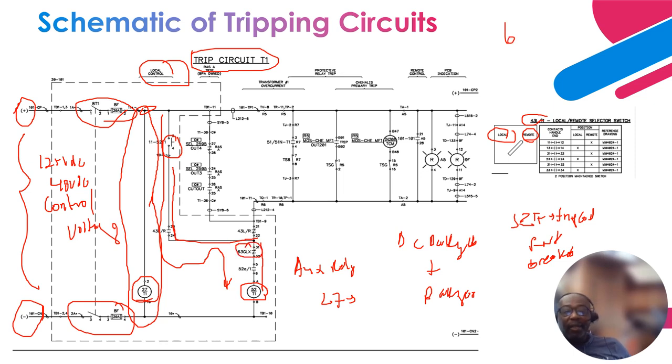So 63GLX is an auxiliary relay, a control relay, right? It is a gas switch relay. Basically, it's measuring the pressure and density of the gas level, right? And remember, there is an adequate gas level based on a set of criteria. There's a set point for gas that is needed for the operation of the circuit breaker.